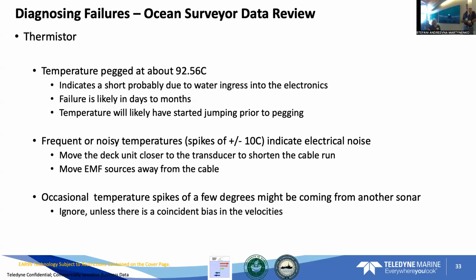Okay. The thermistor is embedded into the transducer, through the bronze into the ceramic, beneath the bulkhead connector. I showed a picture. It goes right through the beamformer, right into the heart of the transducer, the ceramic. So if your ceramic is flooded, that's why you get the reading of 92.56 C, because that's the max for the thermistor. If you get an occasional temperature spike, it's probably coming from something else, or you're getting EMI on the cable. It's not usually that common, but it's an issue.